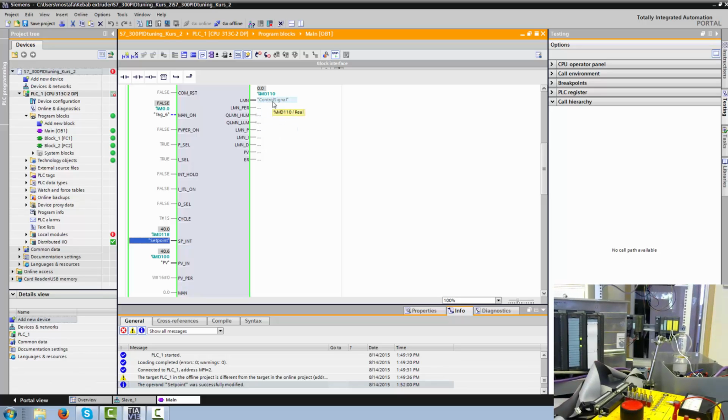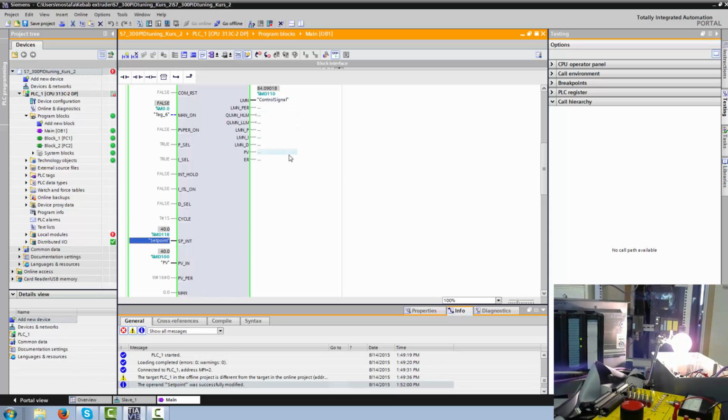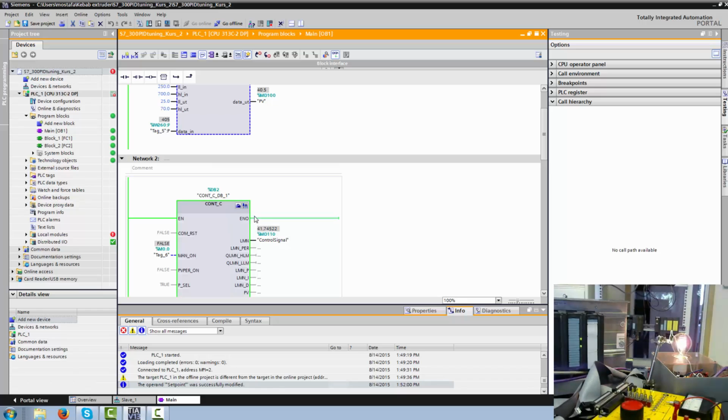We have the integrator, it's too fast, so we have to change the integrator to be a little bit slower. And maybe the P parameter can be increased. So now we have 40, it's going down to 39.8, and the controller is going up very fast. So now we go to our commissioning part to show you how you can fine tune your controller.